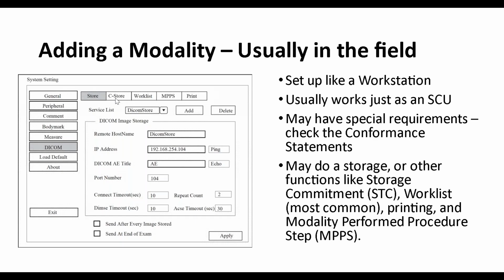They keep one database on that same storage so they can update, or they keep multiple databases and they update each other. But it is entirely possible to use a whole separate network as a storage for a DICOM network. That sounds weird, right? That's what storage commitment is.